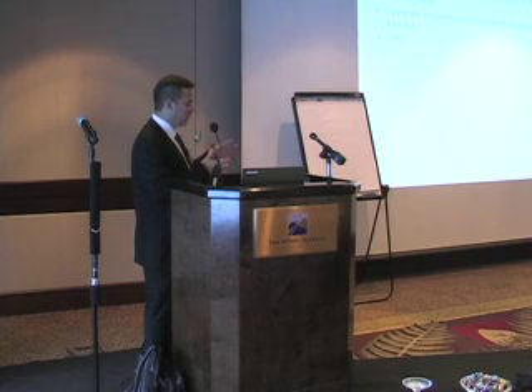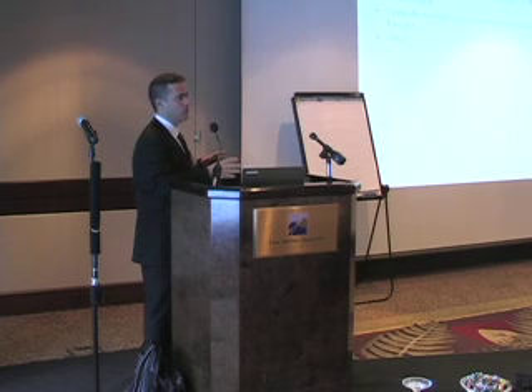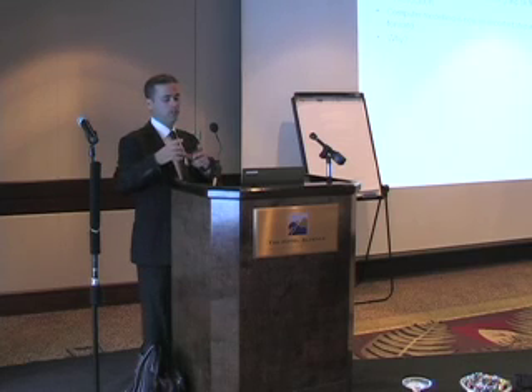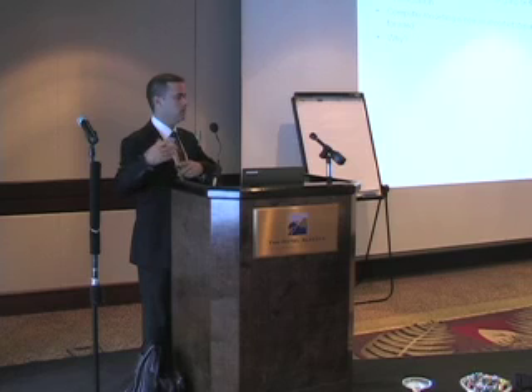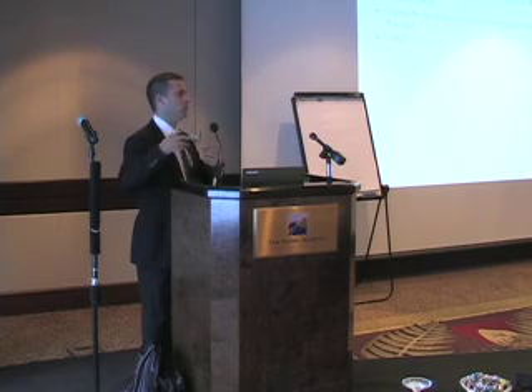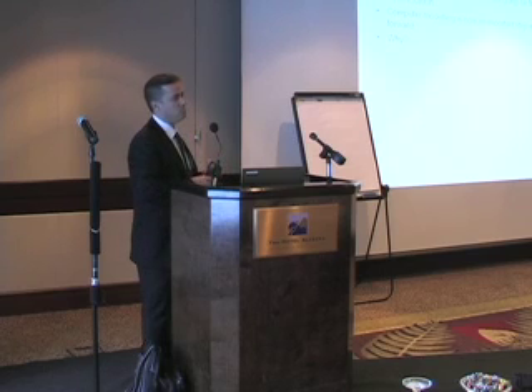We've got guys there that have to model that, like you say, in the beginning, and work out what the fault current capacity of every device is on the network. Therefore, when we switch around to this configuration, we've only got this much fault current capacity to feed into the grid. Should there be a fault, is that enough? No, well then we can't run that configuration. We need to run one more engine or something to that effect, a synchronous compensator, a few other magic boxes out there.